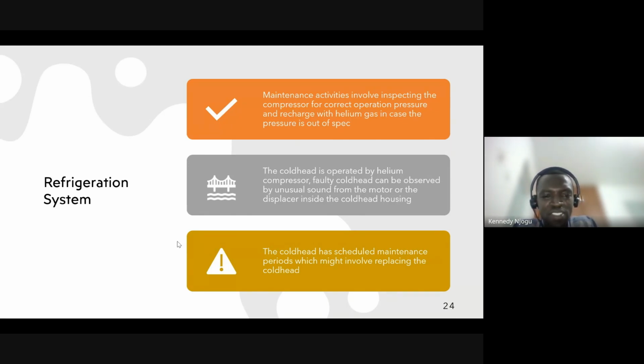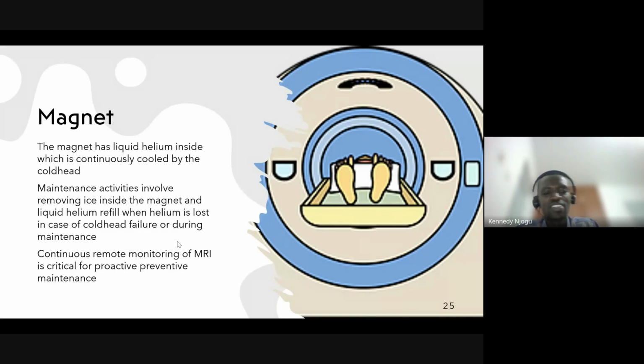Next page, please. Okay, so the magnet has the liquid helium inside. So if you have your cold head running okay and your chiller is running okay, you're barely going to have any issues with the magnet. Some of the maintenance activities we do on the magnet: you can open the magnet and inspect for ice buildup inside. This can be done when the cold head is being replaced. So once you have all this working okay, then you'll not have any issue with the magnet.